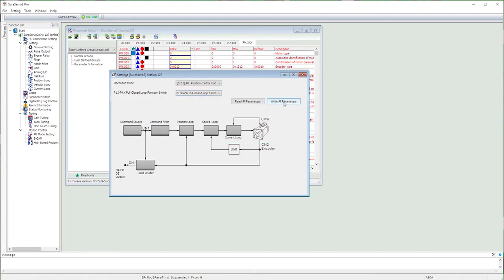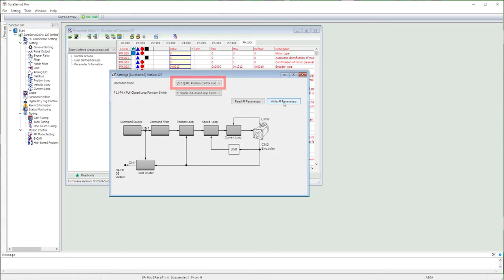If your path doesn't work, then come back here first, click on write parameters and make sure you selected the PR mode. It's really easy to forget to write this to the drive.